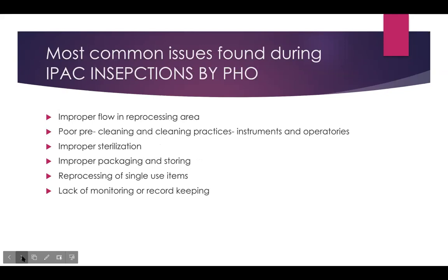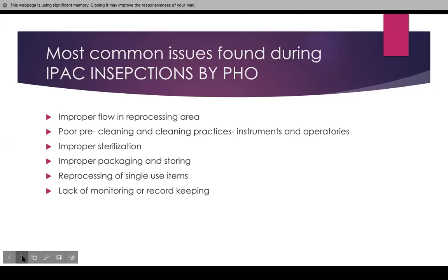The most common issues found during IPAC inspections by Public Health of Ontario are: improper flow in the reprocessing area, poor pre-cleaning and cleaning practices for instruments and operatories, improper sterilization, improper packing and storing, reprocessing of single-use items, and lack of monitoring and record keeping.